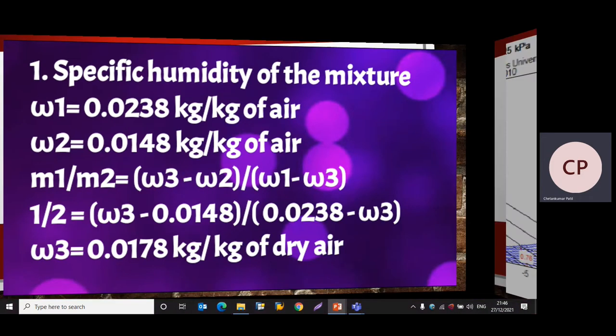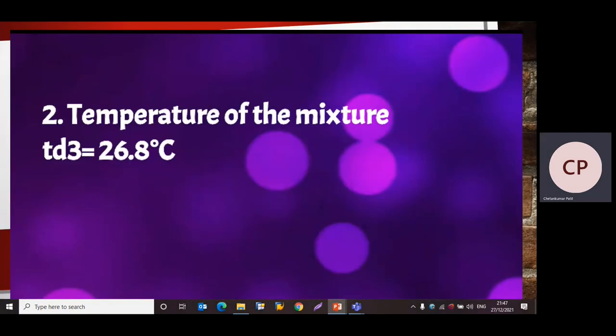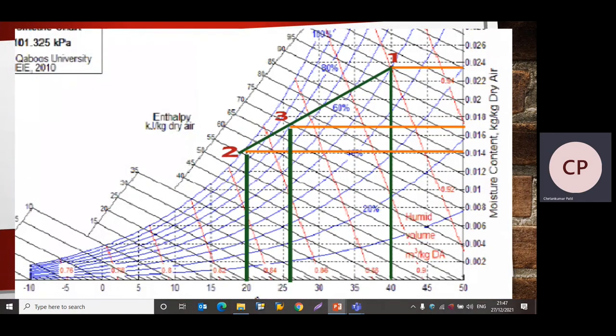With the value ω3 = 0.0178, we draw a horizontal orange line at that specific humidity level. Where this line intersects the green line joining Point 1 to Point 2, that point of intersection is Point 3 — the exact location of the mixture on the psychrometric chart. Projecting Point 3 down to the horizontal dry-bulb temperature axis, we find the mixture temperature td3 = 26.8°C.